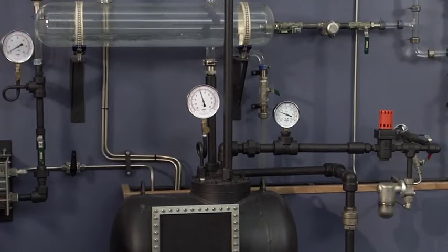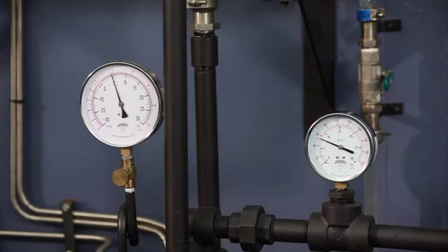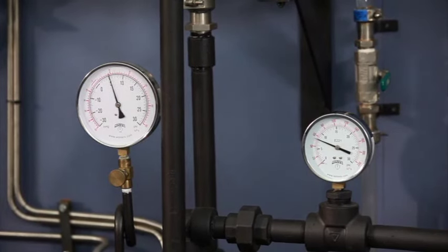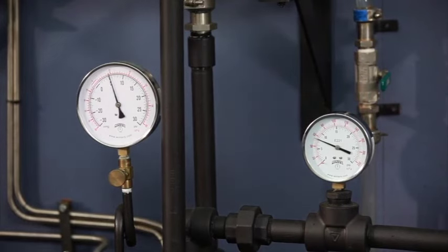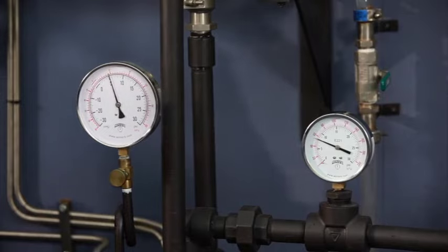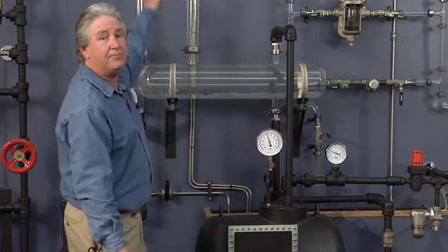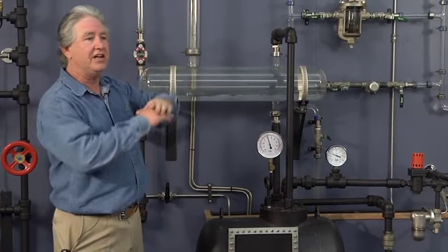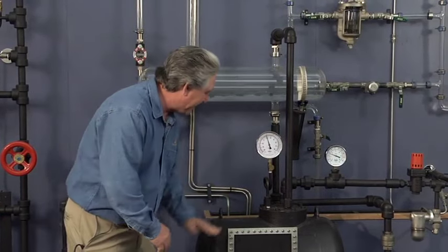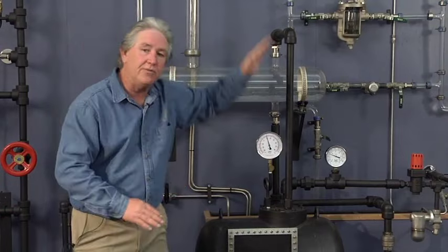Just for you guys that are selling pumps all the time, remember this. Typically, the pump case pressure will never increase over about 10 pounds of what your total back pressure is, where we're trying to pump the liquid to, because by the time the pressure in the pump case builds to that level, the liquid's already gone.